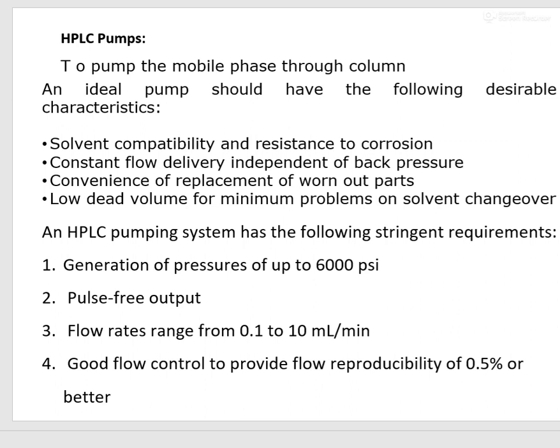Next, low dead volume for minimum problems on solvent changeover. Now what do you mean by dead volume with respect to pump? And what do you mean by solvent changeover? Suppose I am doing method development on HPLC and I am using methanol. Now methanol as a mobile phase is not giving me satisfactory results.